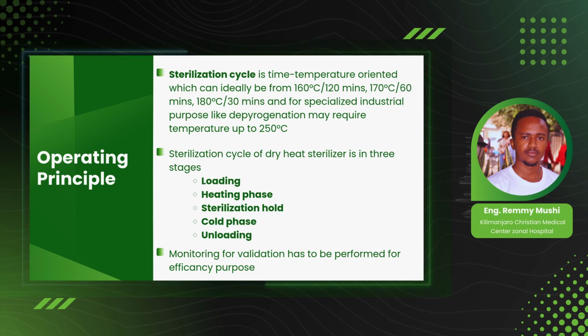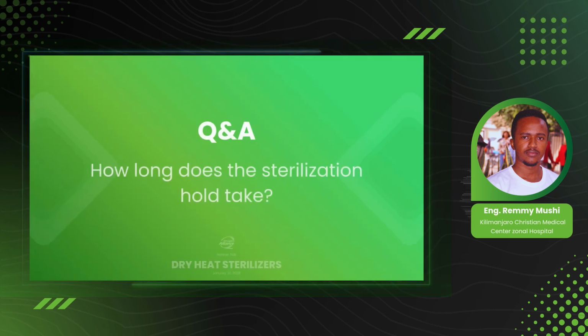All right, thank you very much for that presentation, Mr. Remy. Just wanted to get some clarity. The sterilization hold, how long does it take? It will depend. In many cases, as we have seen with this dry heat sterilizer, some people change the element without considering the chamber volume. So the sterilization hold may vary, but it is required to be around 70% of the time for the whole cycle. If the cycle time was 120 minutes, it means 70% of that 120 minutes is the time needed for the sterilization hold.